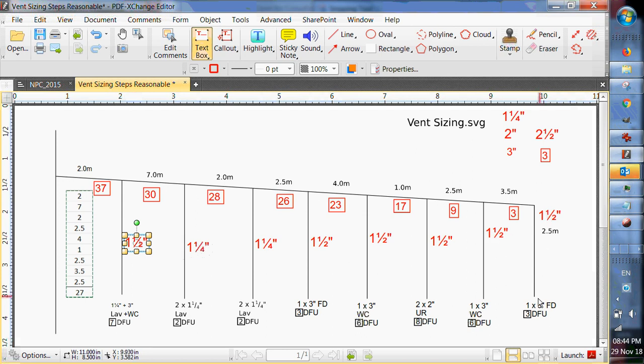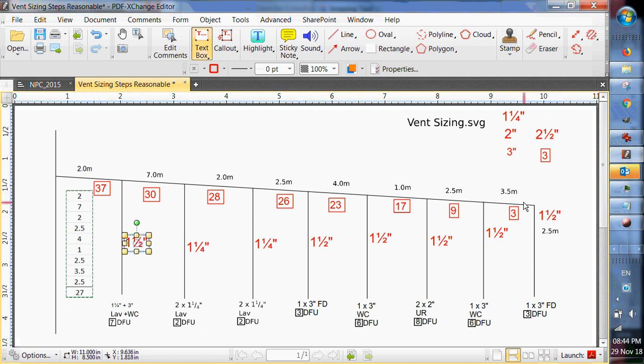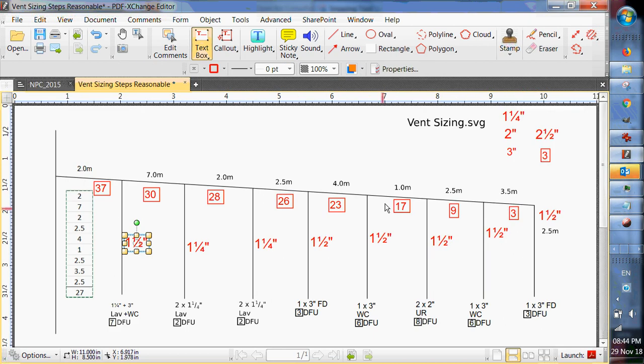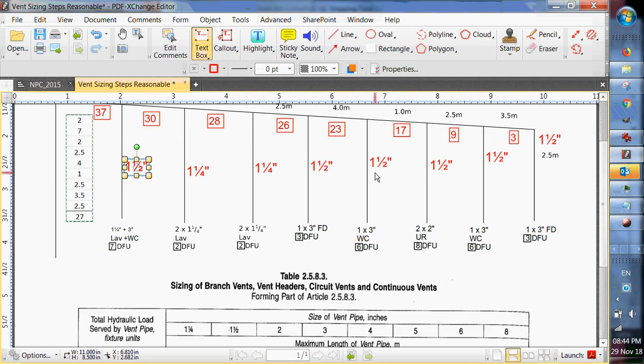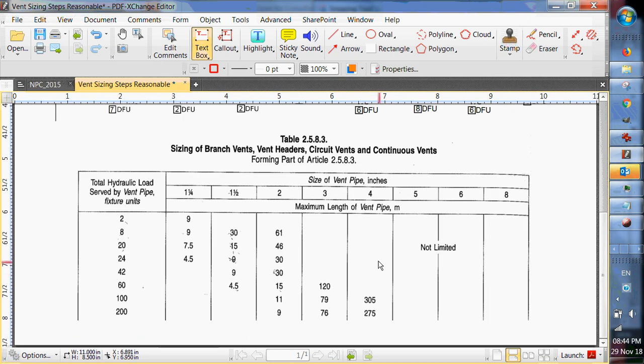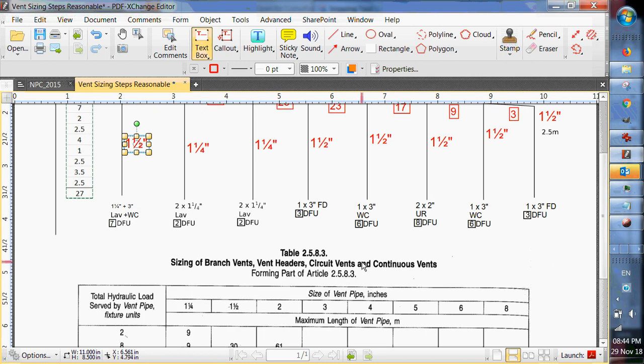So we know we need at least an inch and a half because that's the size of our farthest fixture. It's an inch and a half vent. Now we've got to check it and see if maybe with that 27 meters, maybe we need to upsize this long line here a bit. So let's start looking at our actual sizing table. Actually, I think I put the sizing table right here. I did. Okay.